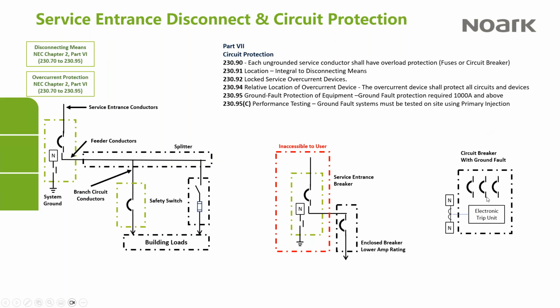This diagram here to the right shows you how an electronic trip circuit breaker does ground fault. You've got the 3-phase currents running through the breaker. And then there's a sensor placed in the neutral circuit that's connected to the trip unit. The trip unit in the breaker measures the phase currents and any current that's flowing through the neutral, and it determines, based on the relative ampacity flowing through each part of the circuit, whether there's a ground fault or not, and it'll trip the breaker.